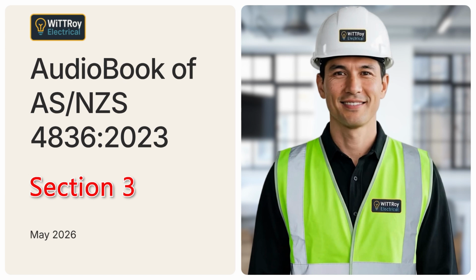If the isolation switch has a locking facility, that locking facility must be used. The securing device does not have to be built into the switch, but it must require a deliberate action to attach or remove it. Examples may include a clip, screw, bolt, pin, padlock, personal danger tag, lockout system, permit system, or another system that gives an equivalent level of safety. In simple terms, isolation must not be left unprotected. It must be secured so another person cannot accidentally switch it back on.